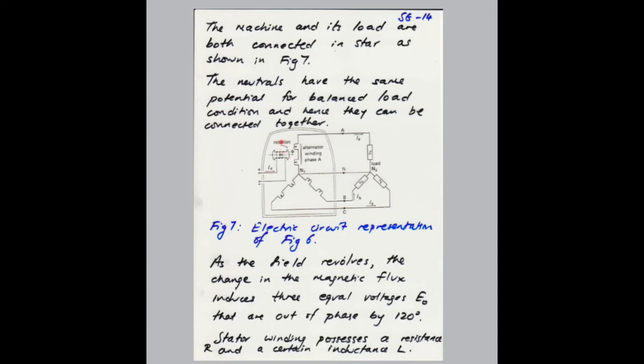As your field rotates, when the rotor turns, the field flux phi will sweep through your stator winding and induce a voltage E0 between phase A and the neutral. Each of the stator terminals will also get an induced voltage of magnitude E0, except that they will be out of phase by 120 degrees. The stator winding for each phase is obviously a coil, so it will have a certain inductance, represented by L, and being a copper conductor, it will also have a certain resistance R.